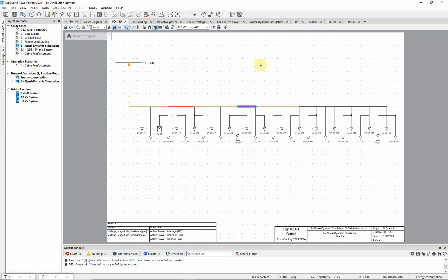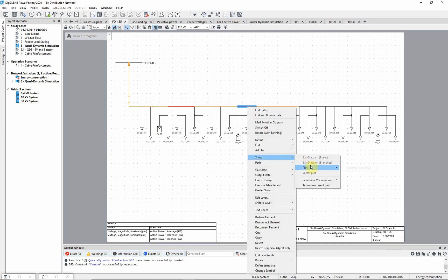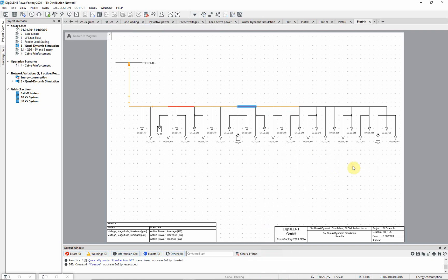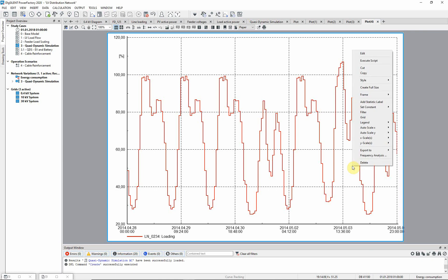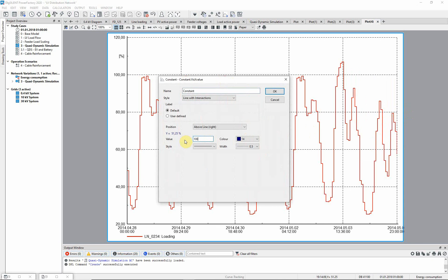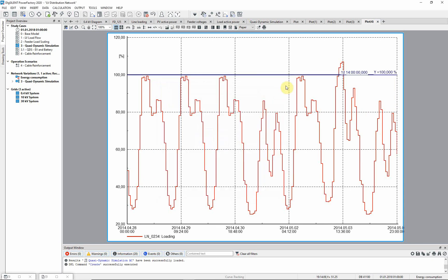On an overloaded line, choose the option Show, then Plot, and then Loading. Here you can see the loading profile for the line over the time period of interest. A line is overloaded if its loading is above 100%; set a constant to illustrate the 100% level. We can also label the point in time where the overload occurs. The highest overload is approximately 107% and occurs at 1 o'clock on the 3rd of May.